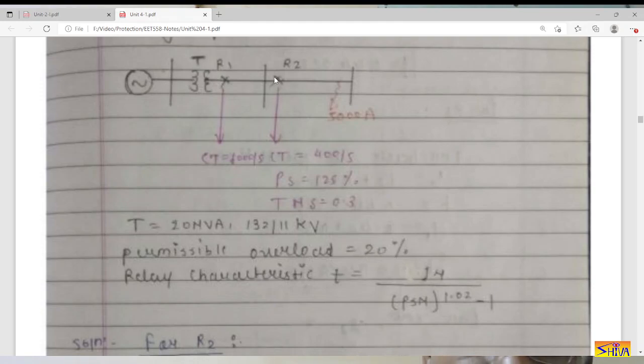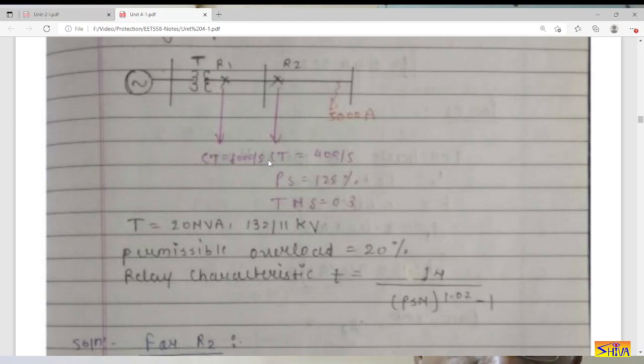This is a slightly different problem. For R2, both plug setting and time multiplier setting are already given. A transformer is given with its rating. The relays are rated for 5 amperes because both CTs have a secondary current of 5 amperes, but the two CTs are not identical — R2 has CT ratio 400/5 and R1 has CT ratio 1000/5. We have to compute the plug setting and time multiplier setting of relay R1, and we always start with the relay at the remote end, R2.